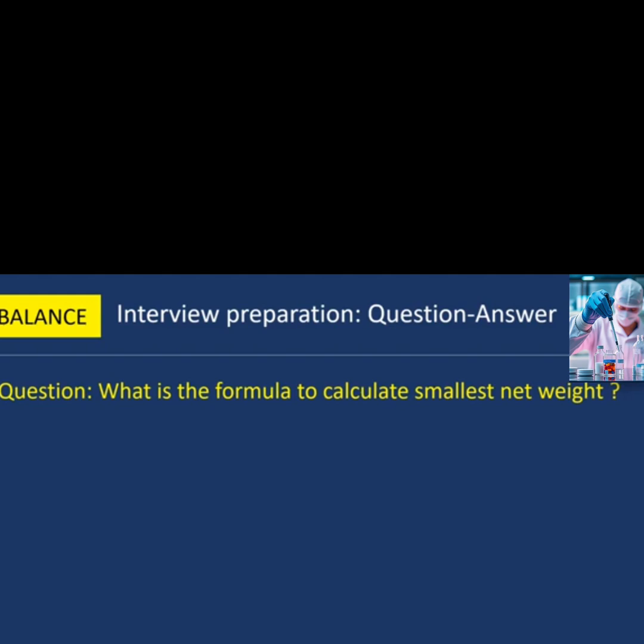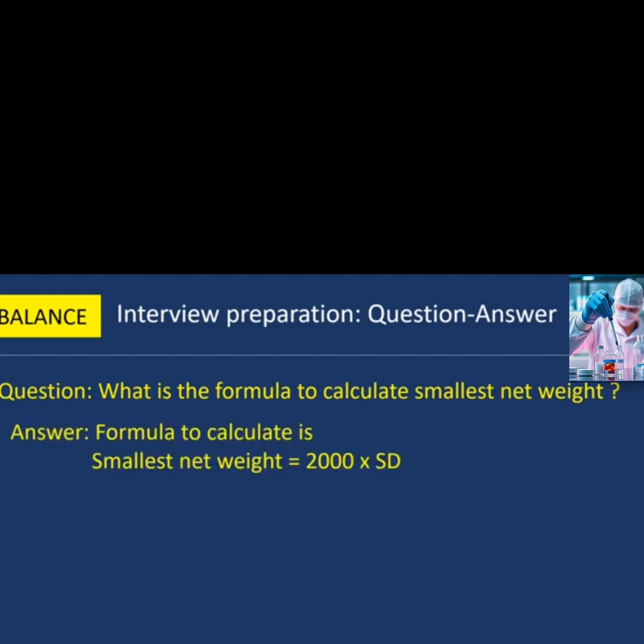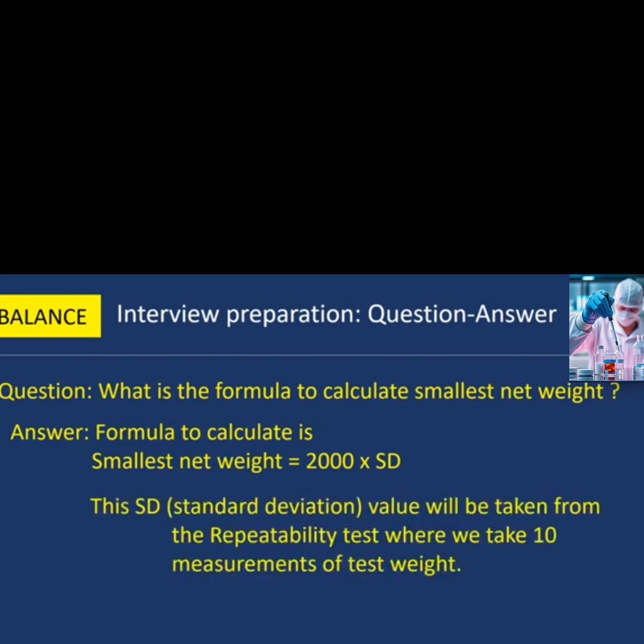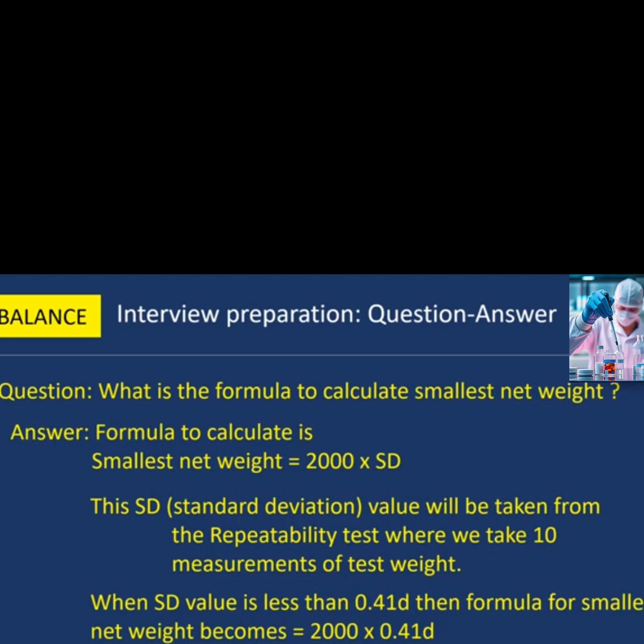Next question: what is the formula to calculate smallest net weight? The formula is: Smallest Net Weight = 2000 × SD, where the SD value is taken from the repeatability test using 10 measurements of the test weight. When the SD value is less than 0.41D, the formula becomes: Smallest Net Weight = 2000 × 0.41D.